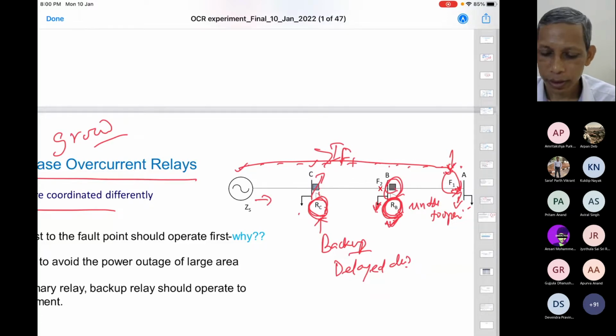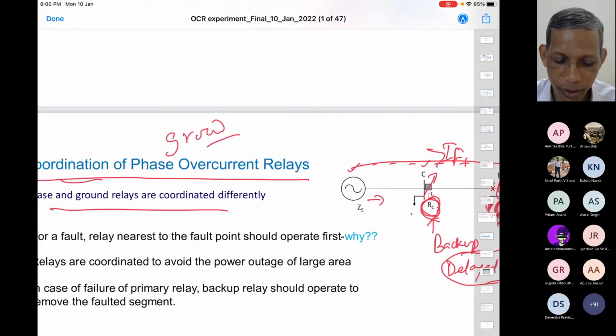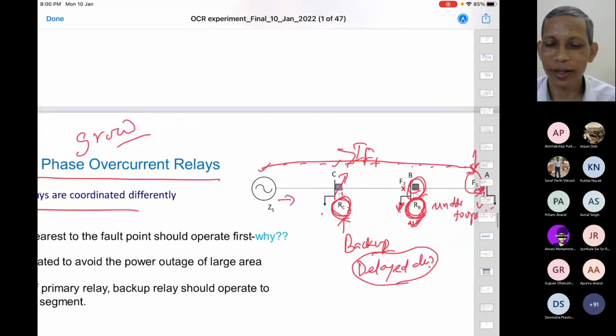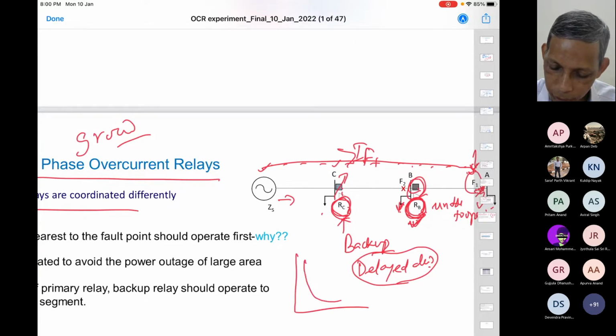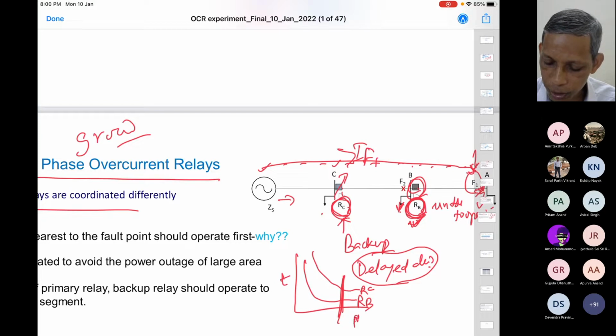So therefore the backup, the delayed decision, is delayed with respect to the operation of RB. How much delay? That will require a coordination, coordination between the RB and RC relay. Like in IDMT characteristics, if this is the corresponding relay characteristic for RB, the RC relay should be here. Is it okay? For the same level of current, this is the time information, and this is multiples of PSM. For the same level of current, as you notice here, the decision time of RC should be more.